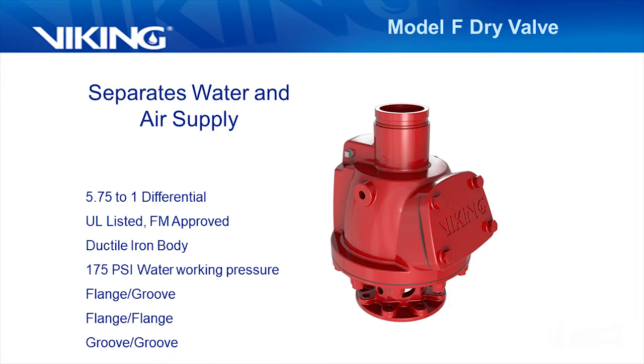So there's the valve, with some basic specs. Like I said, the 5.75 to 1 differential is what keeps that clapper closed. It's UL listed, Factory Mutual approved, and rated for 175 psi of water working pressure.